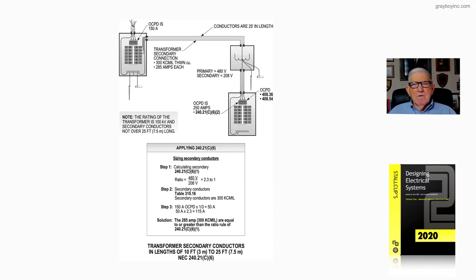Primary is 480 volts. Secondary is 208 volts. And the secondary, these conductors are 300 kcmil THWN 285 amps.